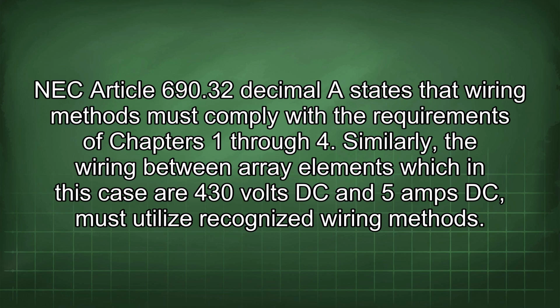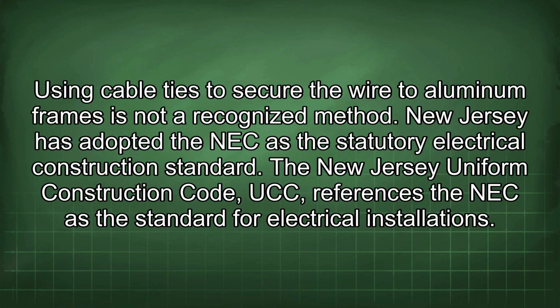NEC Article 690.32 states that wiring methods must comply with the requirements of Chapters 1 through 4. Similarly, the wiring between array elements, which in this case are 430 volts DC and 5 amps DC, must utilize recognized wiring methods. Using cable ties to secure the wire to aluminum frames is not a recognized method.